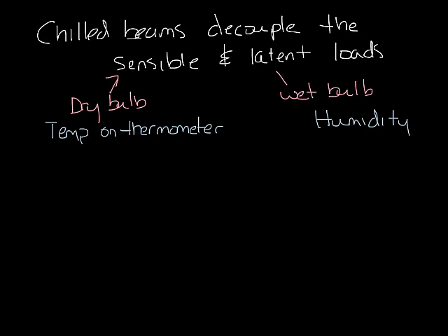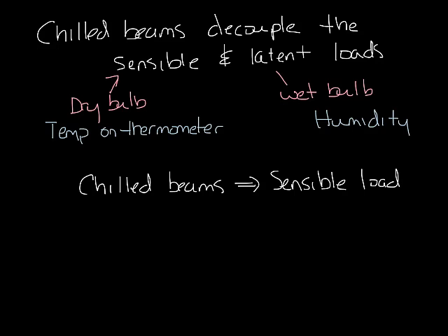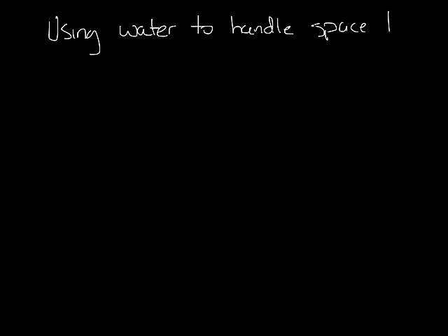Like I said, chilled beams allow you to decouple the sensible and latent load, so the chilled beam itself handles the sensible load in the space. The latent load is typically handled with a dedicated outdoor air system, or a DOAS system. The DOAS system dehumidifies the outside air before it enters the primary air stream. One big benefit to this is that you're using water to handle the space load, and water is a much more efficient way to transfer energy.